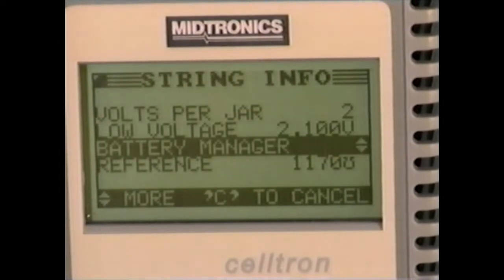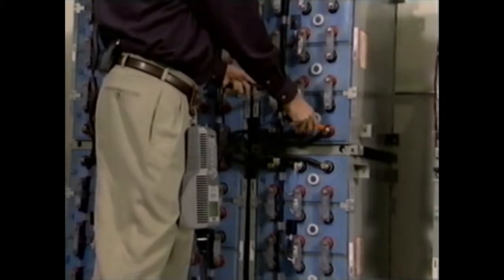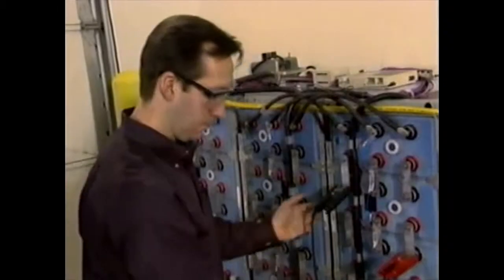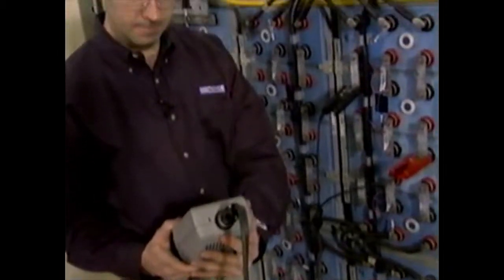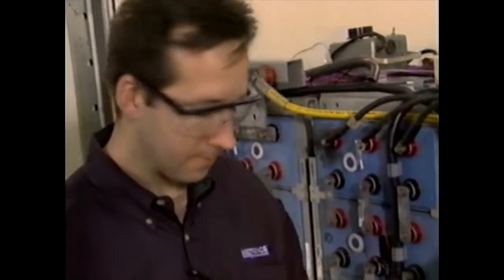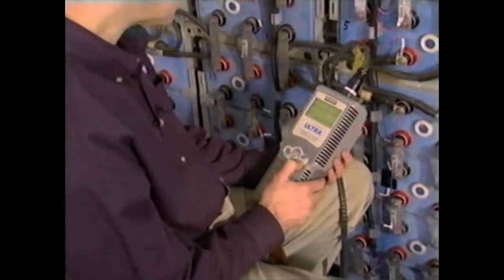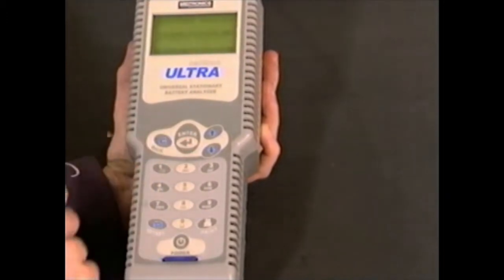The idea is to match reference values to the actual models you're testing. But suppose the models you're testing do not match any in the CELLTRON ULTRA database. You can have the analyzer create a reference standard based on the values of the batteries you are actually testing. This value is based on a percentage of batteries that have the highest conductance value. Here's how to set it up: select battery manager.